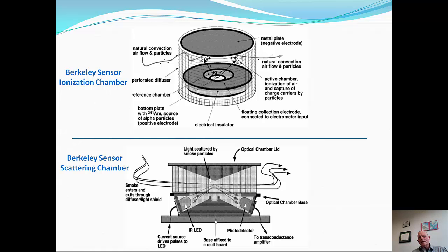But inside this little chamber, you can measure the numbers of very, very small particles all the way down to 5 or 10 nanometers without too much difficulty. To compensate for particles at the high end, you also want to measure how many there are of them as well. This is a simple scattering chamber.